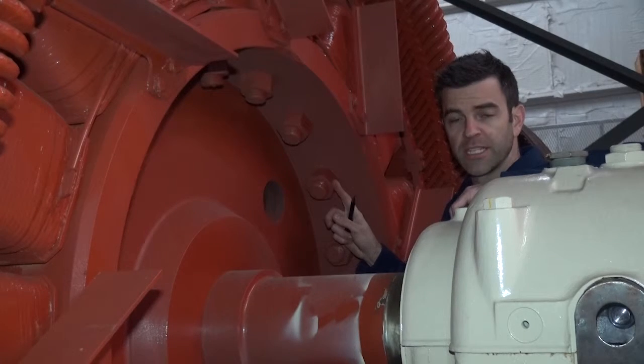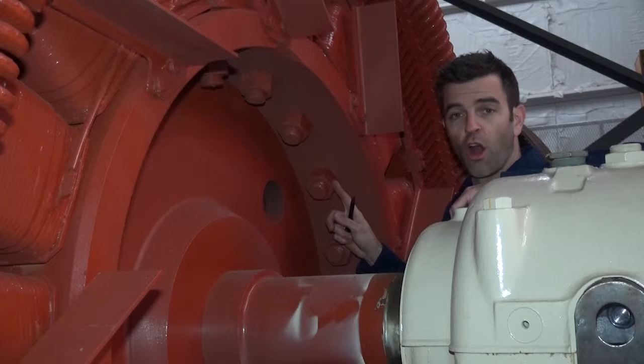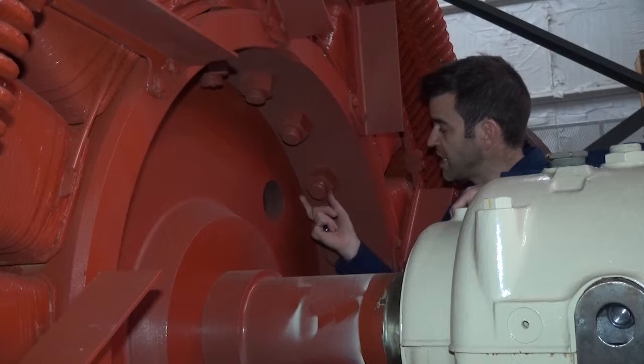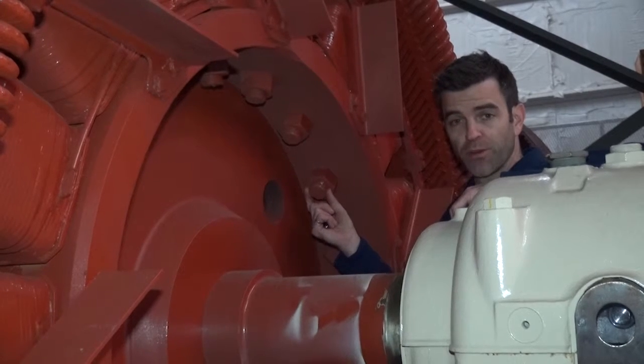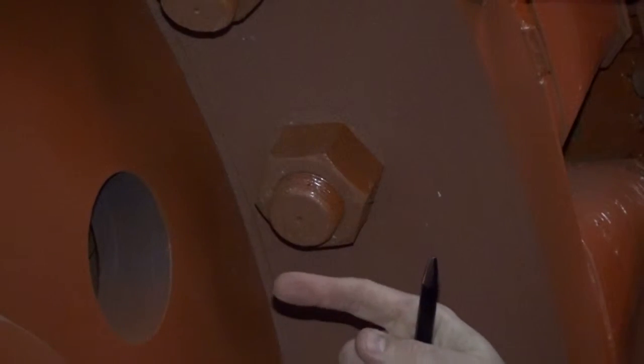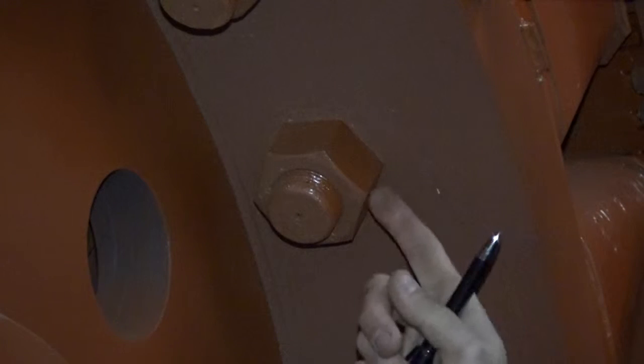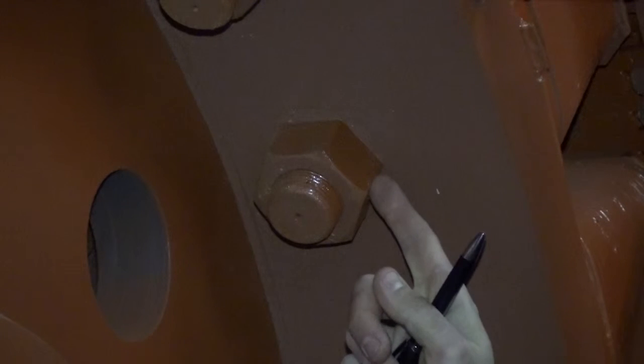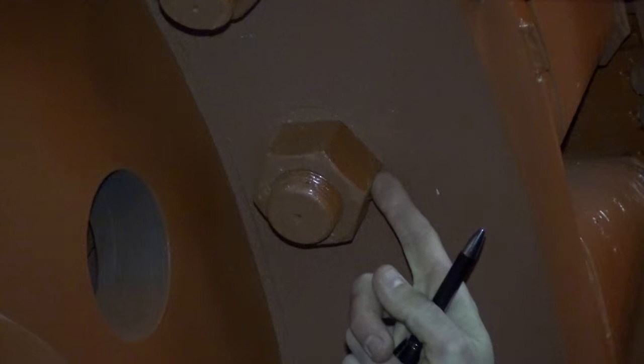Another important inspection point on the motor are the pole bolts. You can see here that there are studs protruding from this spider assembly upon which the rotor poles are mounted. Each pole in this case has one stud on each side, or two in total. Some motors will have 4 or 6 bolts or studs per pole assembly.